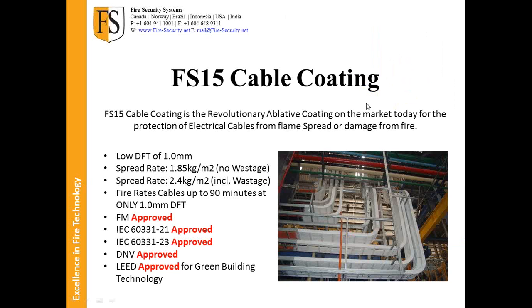So our FS15 cable coating. It's an ablative cable coating, not new to the market. It's been here for a while, but like I said, it's an ablative cable coating. And ablative is basically the same chemical type of reaction that dry ice has. What it does is it lets non-toxic, non-hazardous gas under heat come out of the coating, and that starves the oxygen around the cable. And therefore, with no oxygen, the fire does not spread.